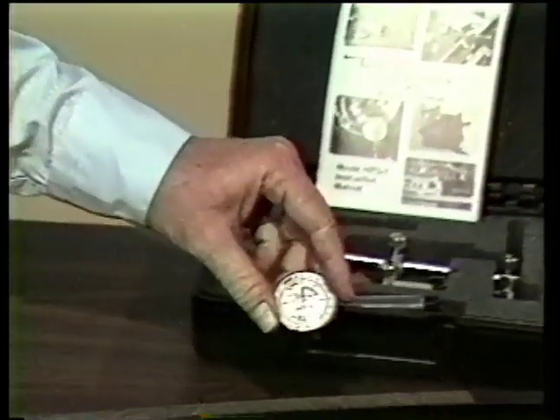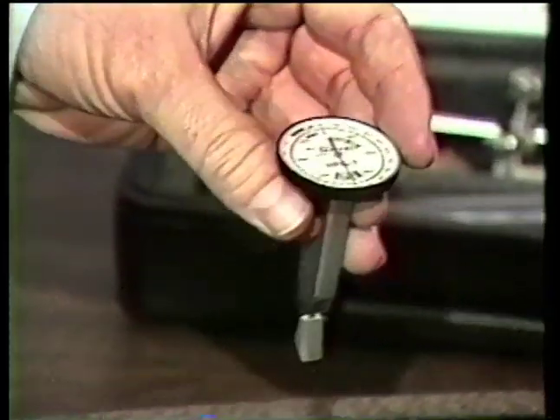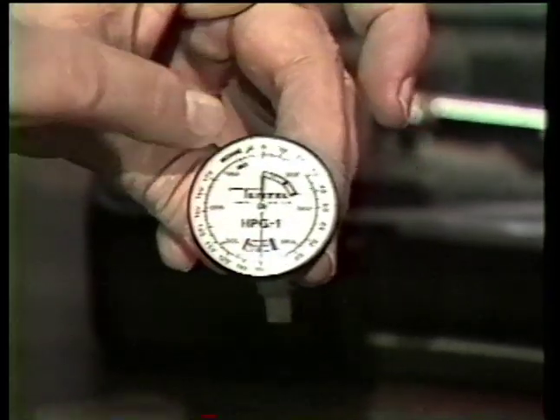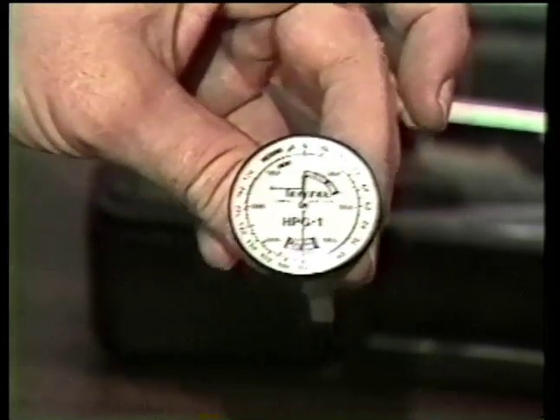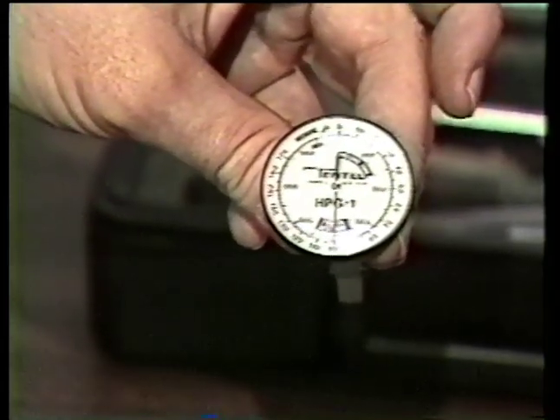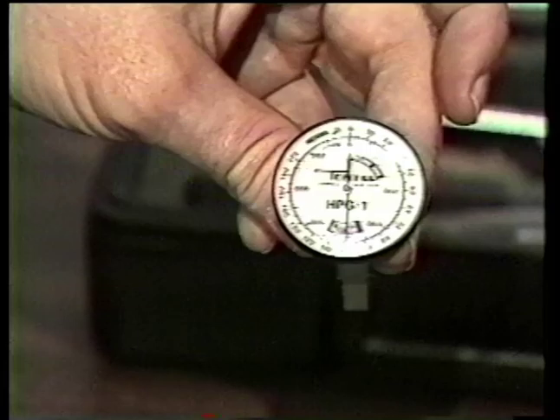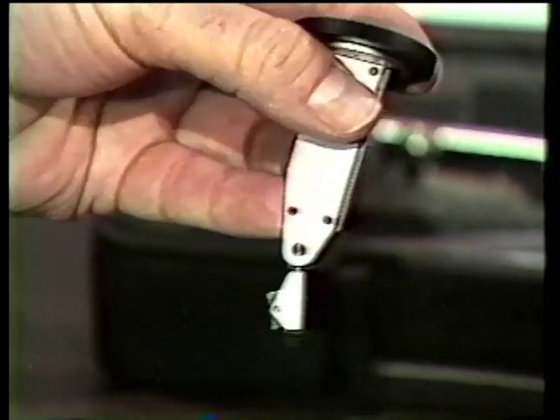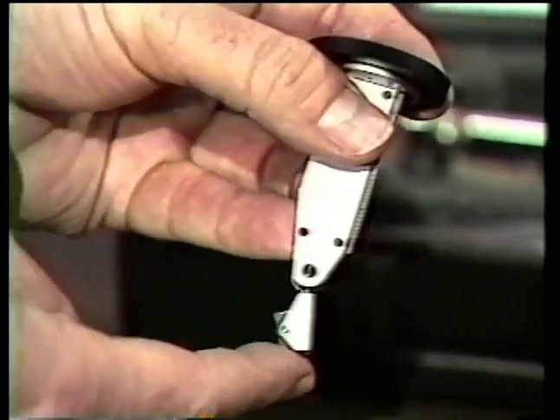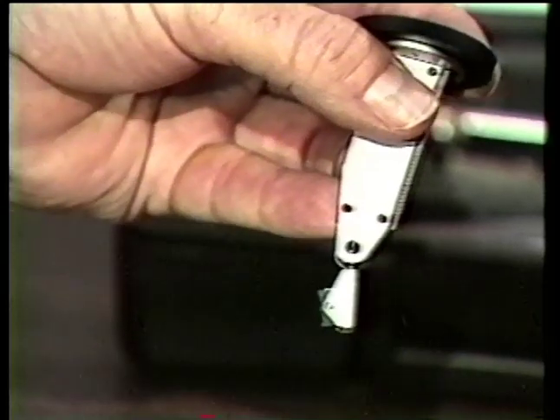First of all, there's the little indicator itself. This is the heart of the device. The indicator, you'll note, is calibrated in both microns and 10,000ths of an inch for that very accurate reading to show where we are along the wear cycle. The other end of the indicator has a little self-aligning plastic foot that actually rides on the drum.